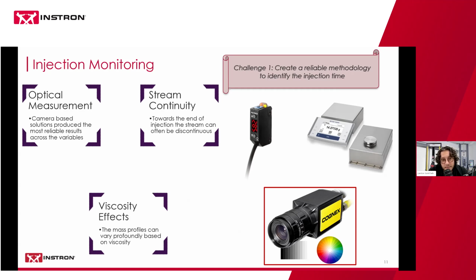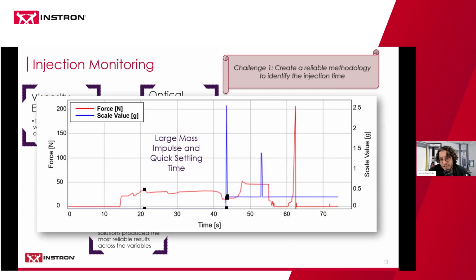And like I said, there can be issues with stream continuity, especially for higher viscosity fluids and spring based devices. As you get towards the end of that travel of the spring, it'll push less and less. So you tend to get discontinuous drops of fluid towards the end of your injection, which can be really difficult for a laser or for a scale. I'll show you what those viscosity effects can look like on the scale readings. In this first graph, the blue is the scale value. This is an extremely low viscosity fluid, and you have a very large impulse of mass, and then it settles extremely quickly.